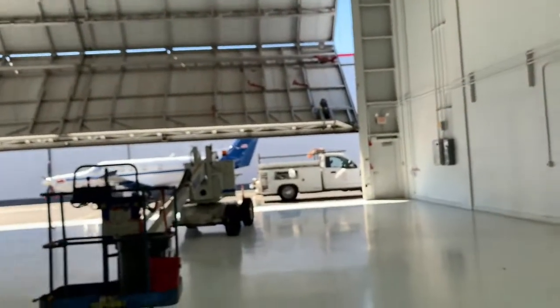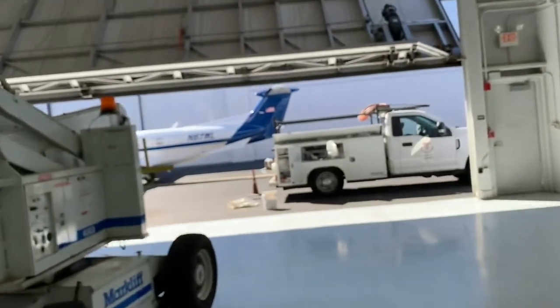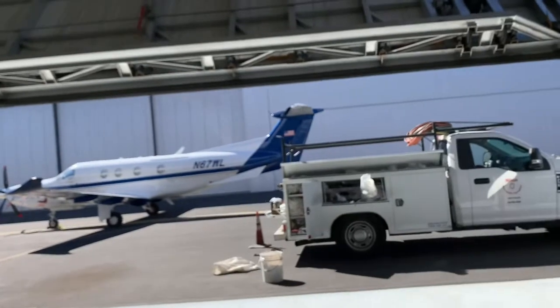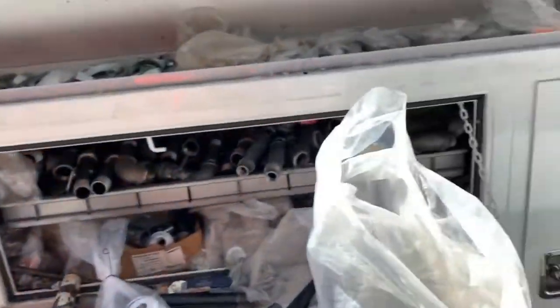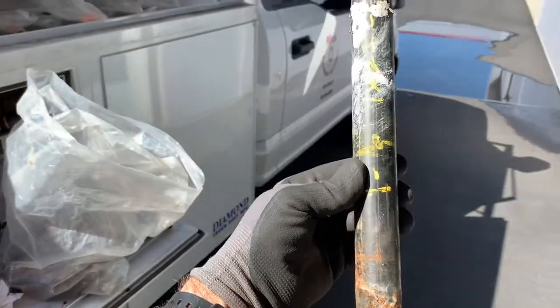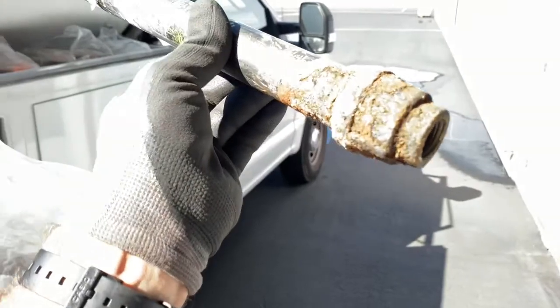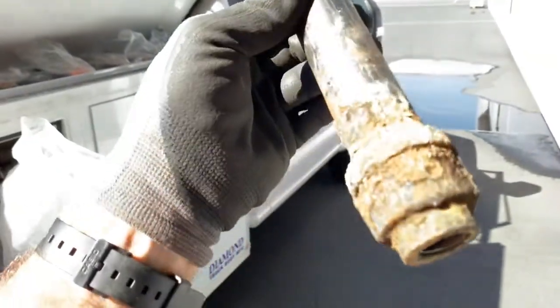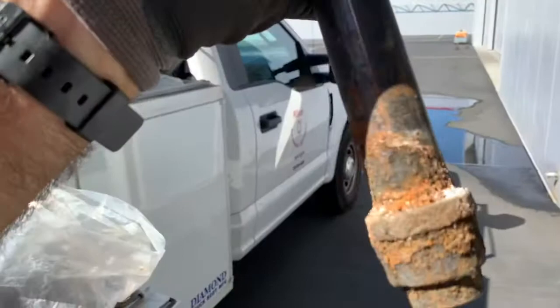So you pull the pipe out and you stick another piece of pipe in the hole and it doesn't fit because the studs are tight around the whole thing. Let me show you the piece of pipe I had to tear out. That right there is what I pulled out. I don't know what kind of bell reducer — one by three-quarter with a bushing. Where it was leaking — it wasn't up here at the threads, it must have been down there at the bushing.